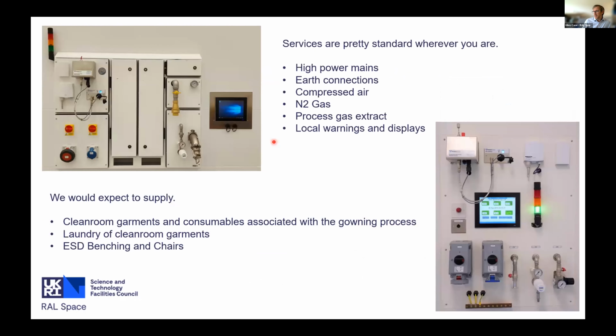We provide a standard set of interfaces and services right across all the clean rooms. They're presented slightly differently depending on where you are, but they're all quite common - high power mains connections, earth connections for grounding, compressed air and nitrogen gas, a process gas exhaust extract system, and local warnings and displays. You can see the screens and beacons in the areas to tell you when something's going out of specification.